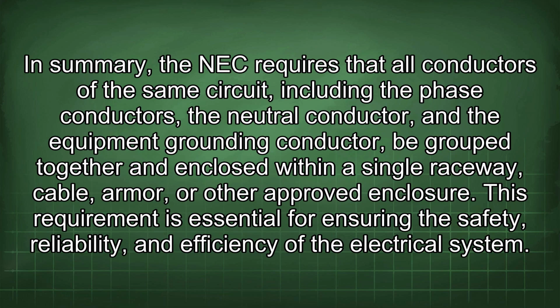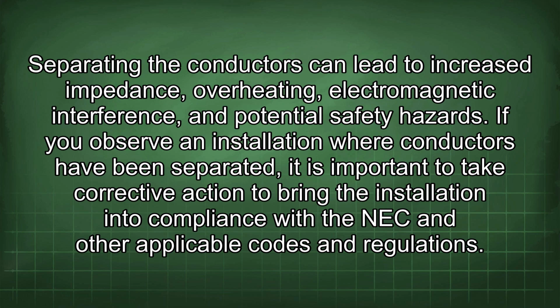In summary, the NEC requires that all conductors of the same circuit, including the phase conductors, the neutral conductor, and the equipment grounding conductor, be grouped together and enclosed within a single raceway, cable, armor, or other approved enclosure. This requirement is essential for ensuring the safety, reliability, and efficiency of the electrical system. Separating the conductors can lead to increased impedance, overheating, electromagnetic interference, and potential safety hazards. If you observe an installation where conductors have been separated, it is important to take corrective action to bring the installation into compliance with the NEC and other applicable codes and regulations.